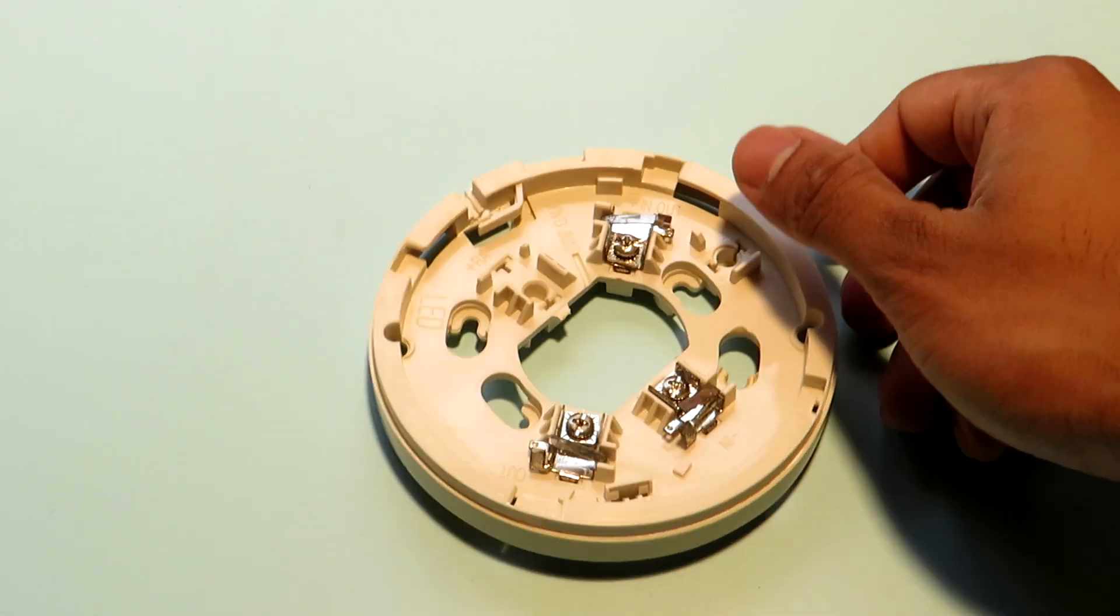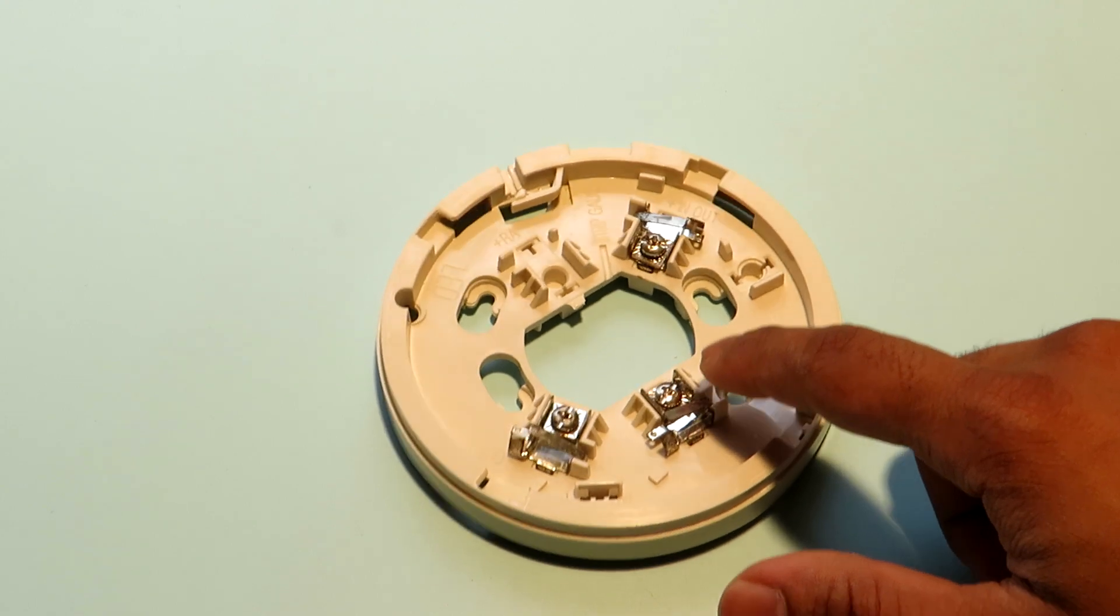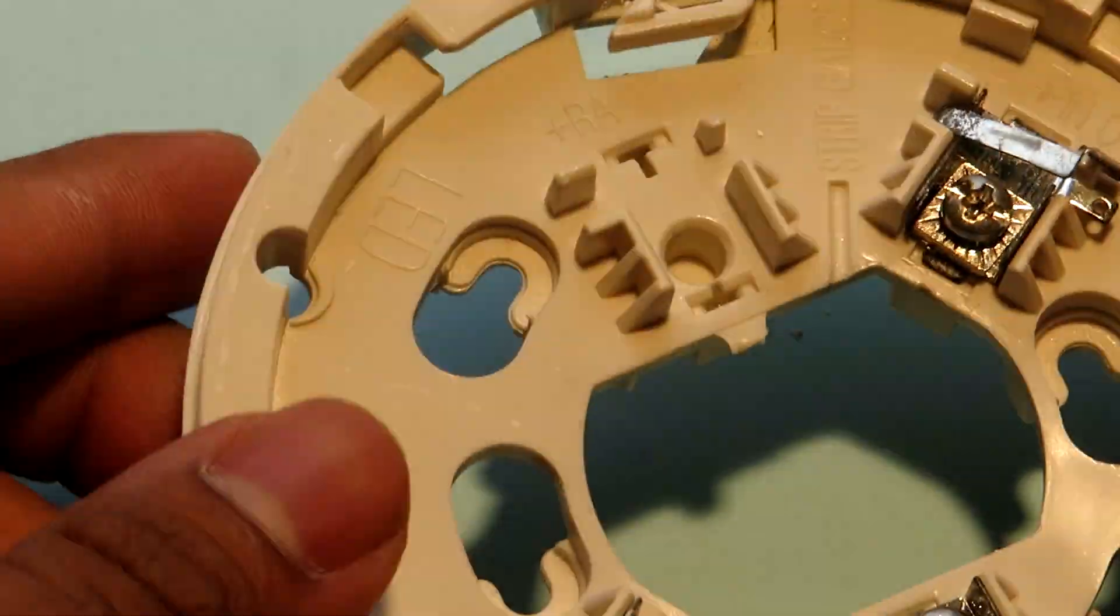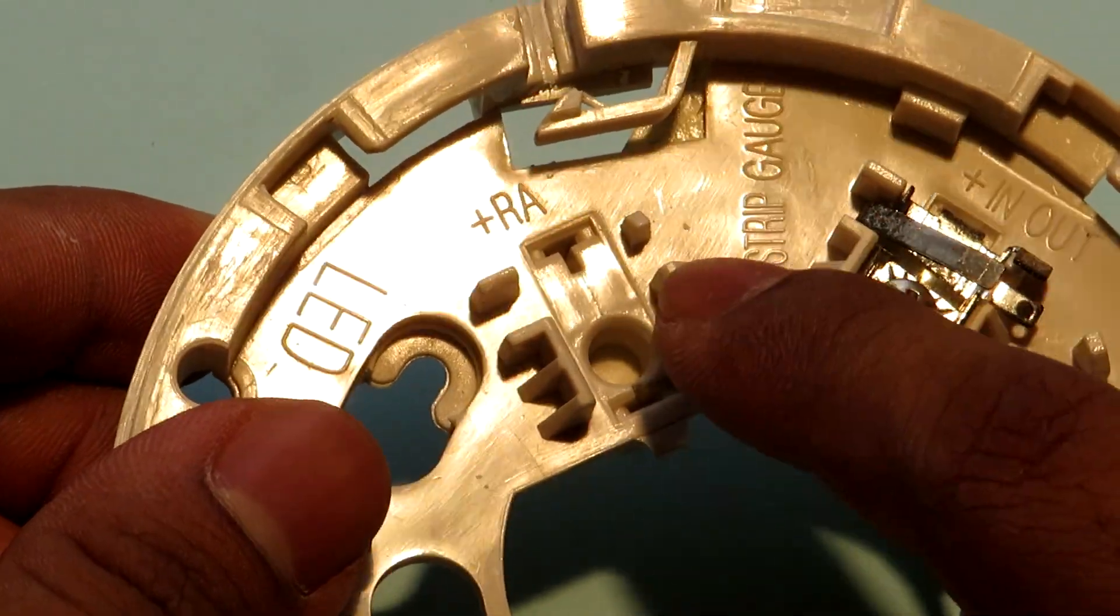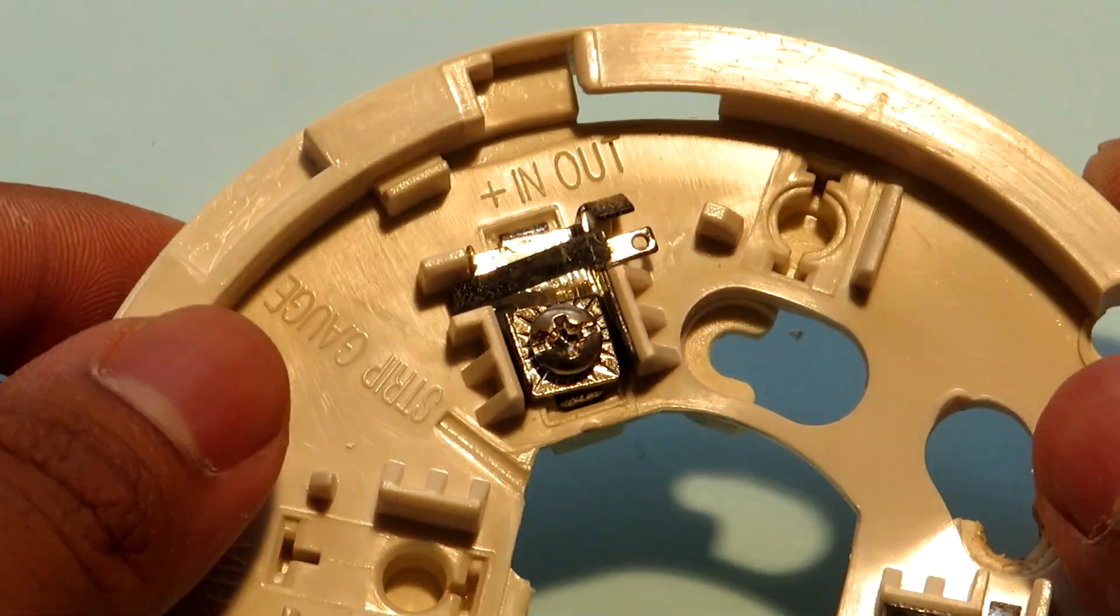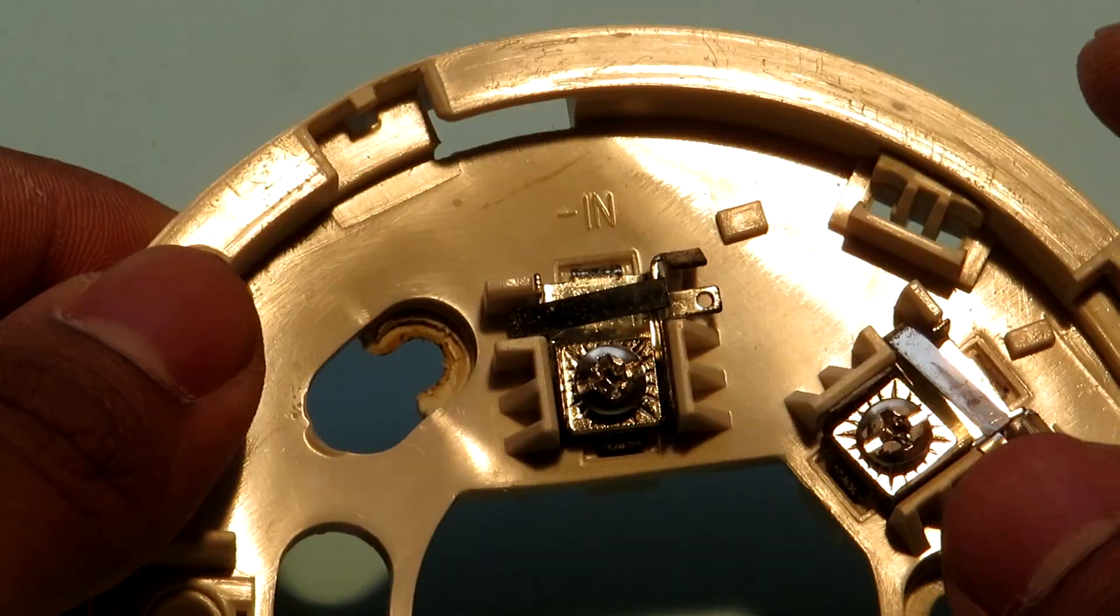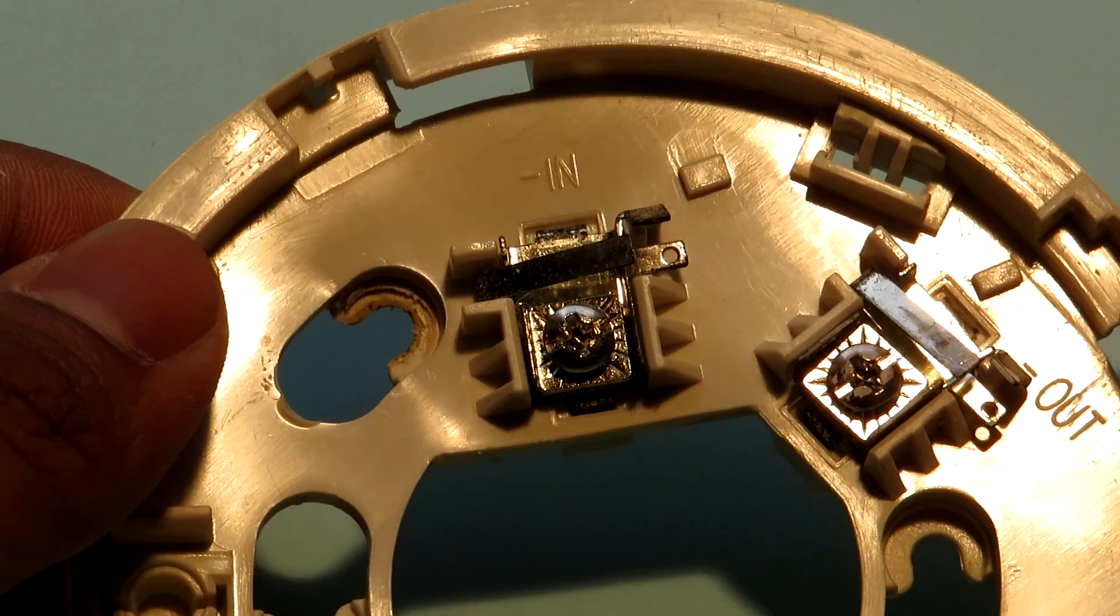Now here you can see something very similar to what we saw in the schematic earlier. There are three terminals and they do whatever was explained in the schematic. There is a provision for a fourth terminal here which has plus RA and LED written over there but there is no terminal. That is given for an auxiliary remote LED in the line. However, our detector does not support that so it has been blanked off by the manufacturer.